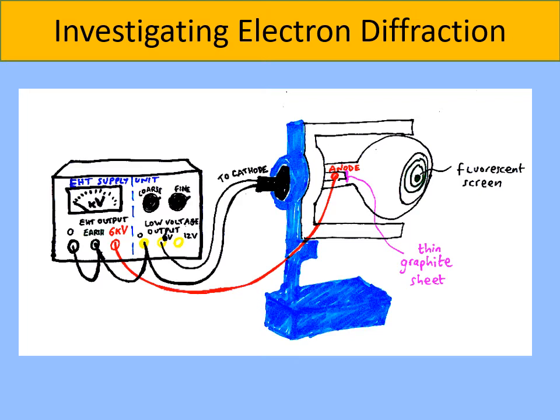Now, it is safe. The reason it is safe, because we're obviously dealing with very, very high voltages. It's safe because there's a high value resistor in series with the high voltage supply, which is shown on the left hand side. This EHT supply unit, I've drawn a little blue dashed line just to show the high output, and there's a low output voltage on the right hand side. Okay, so there we have the resistor in series with the high voltage supply, just so that the maximum current that you can get out of it is not really big enough to do any harm.